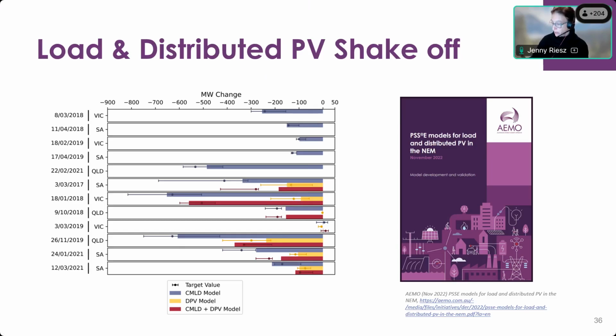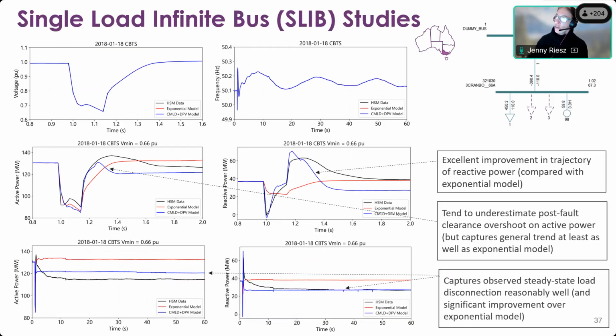So an enormous amount of effort from the team around calibrating those parameters and getting it to represent those shake-off behaviors. A lot of the recent focus has been around validating the transient behaviors of the models as well. For this, we've been doing single load infinite bus studies, where we essentially play back the voltage and frequency measured at a particular bus in the network at a radial location, and then aim to replicate the active and reactive power responses measured at that location.